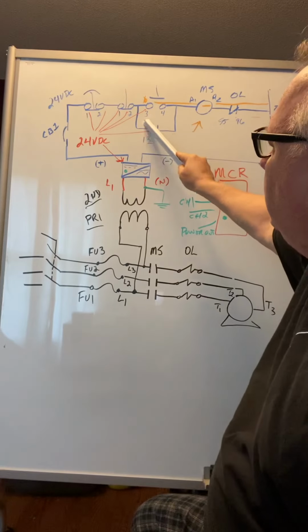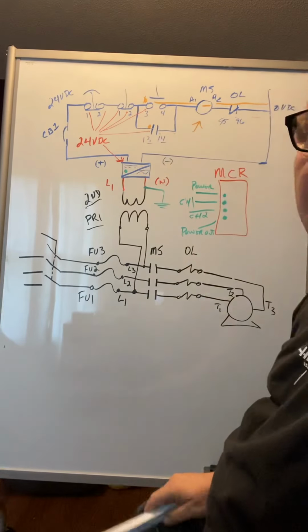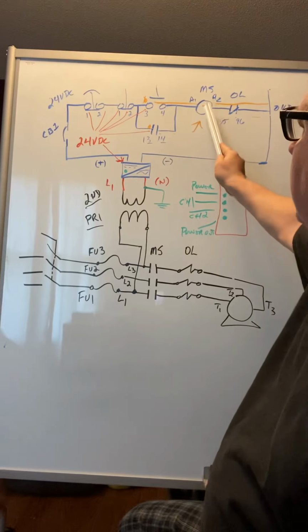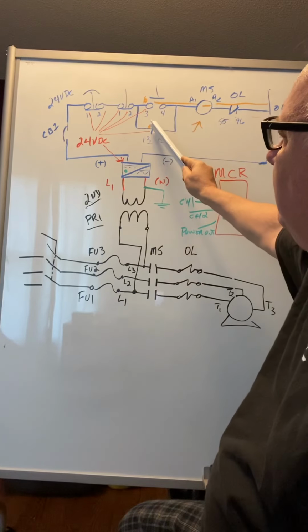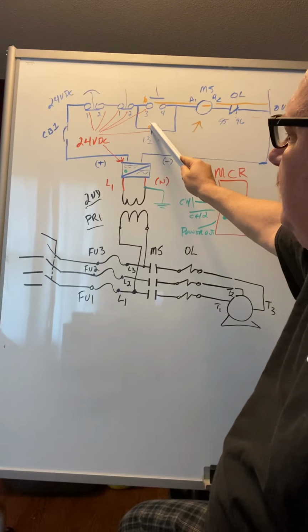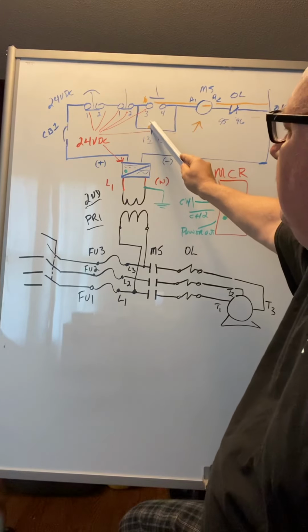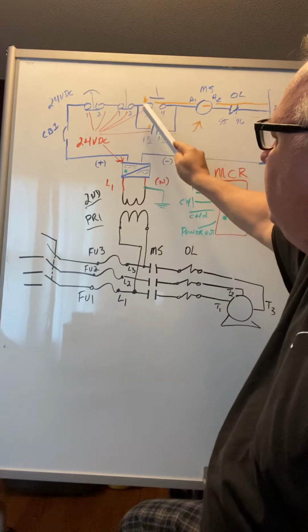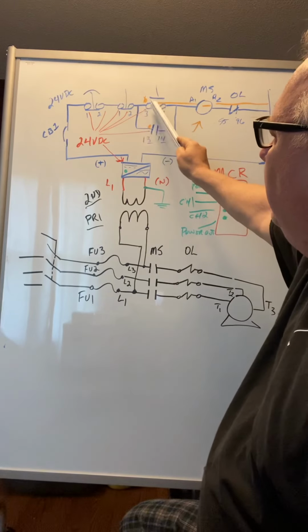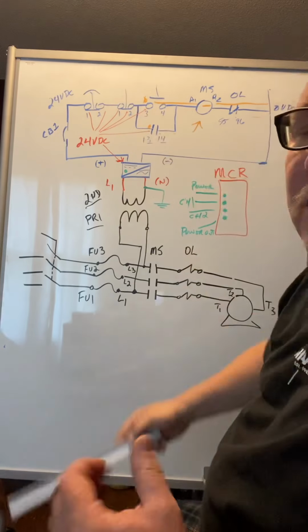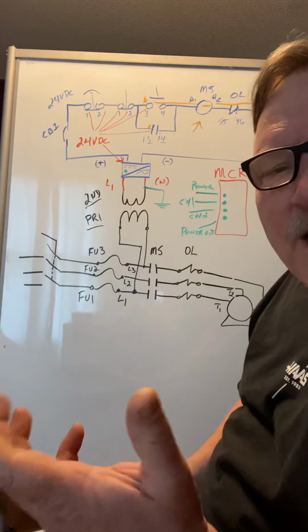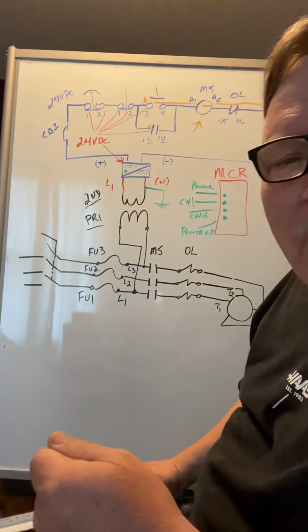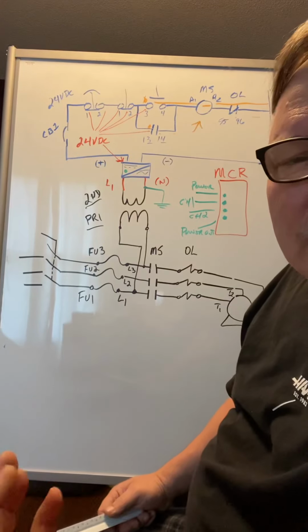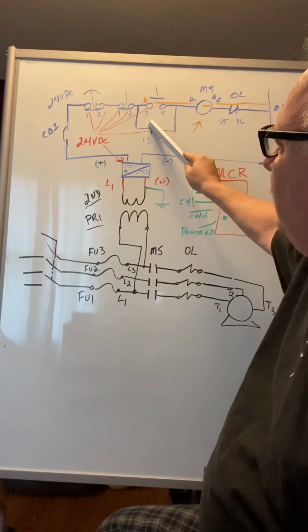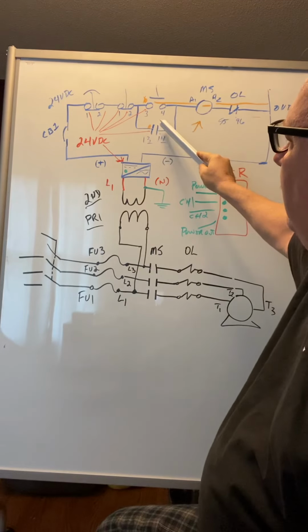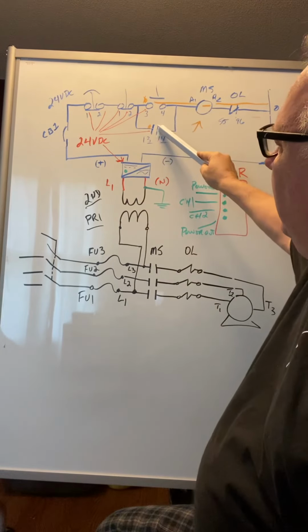Where your problem that you need to start looking at is whatever you're using for this normally open contact that this armature controls, okay? That's where you want to check, do I have my 24 volts here at terminal 13? If you don't, you're going to start backtracking that to where this terminates. Sometimes this will terminate back here at number 3 or number 2. It might go to a terminal rail or something like that, but either way, find out where the source is, where you should have 24 volts on that wire. And if you don't, then backtrack it again. But that's the bottom line. You have to have 24 volts here.